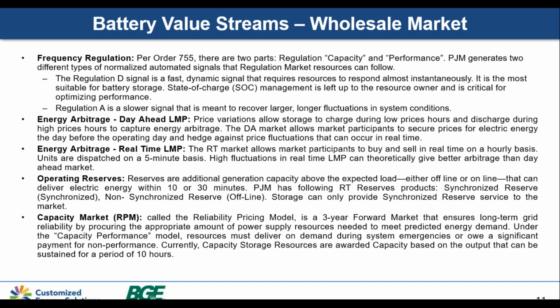In talking about frequency regulation, the storage assets are required to respond to grid needs on a second-by-second basis, though it's an hourly market. Participation in this market really does require a lot from the battery in terms of cycles. So in modeling, we need to consider participation in regulation against the potential long-term degradation of the system. More cycles, or more use of the battery on a daily basis, can have an impact on the capability of the battery in the long term.